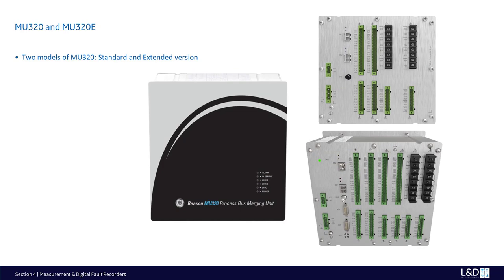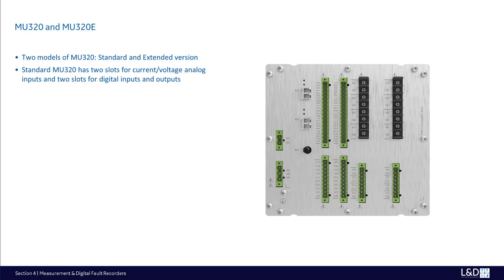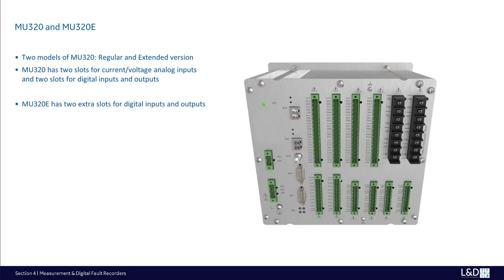There are 2 models of MU320 in the market now: a regular MU320 or standard MU320 and MU320E, extended version of MU320. Standard MU320 has 2 slots for current, voltage analog inputs, and 2 slots for digital inputs and outputs. The number and function of the slots are fixed. MU320E has 2 extra slots for digital inputs and outputs.